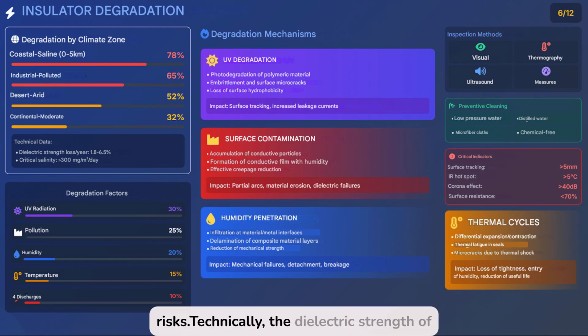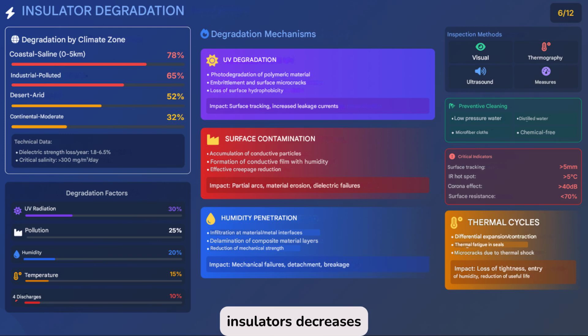Technically, the dielectric strength of insulators decreases between 1.8% and 6.5% annually. Above certain salinity levels, more than 300 milligrams per square meter per day, deterioration accelerates. Factors such as UV radiation, 30%, pollution, 25%, humidity, 20%, temperature, 15%, and electrical discharges, 10%, act together, progressively weakening the material. Solar radiation damages polymers, generating microcracks and loss of hydrophobicity, which favors current leakage.